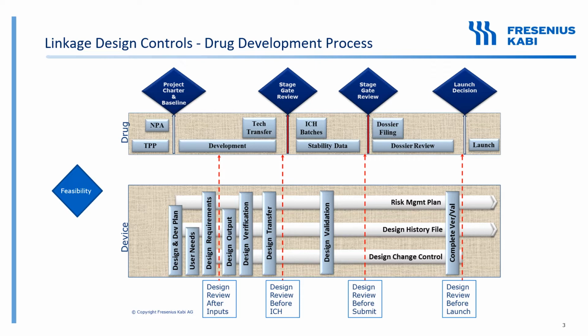So after a target drug has been identified by the business unit, then a cross-functional team helps determine the feasibility of the project. So do we have an in-house device that we already utilize for similar combination products, or do we need to explore platform devices? These are single platforms that can be used across various user groups and disease states. An example could be a pen injector where the manufacturer of the pen develops the device but does not develop the drug. They may sell the device to multiple drug manufacturers.